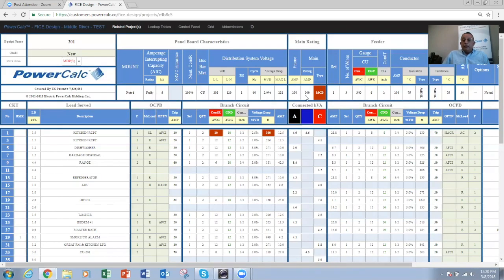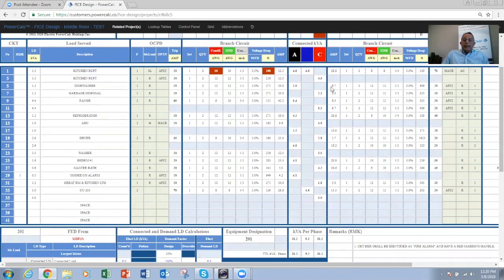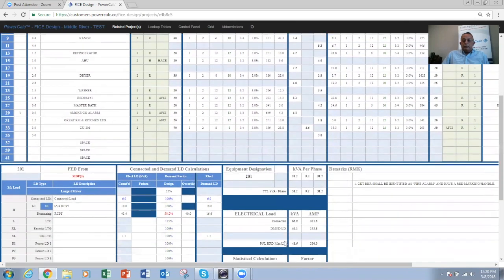It took out the red marking or the red background to indicate to you now you are set on auto and it's not on manual anymore. The system by itself already recommended to you that the frame is for 200 and figured out for you exactly the conductor size, 1, 3/0 conductors, and then the ground is number 6 in a 2-inch conduit. And that's based on this particular demand load. Actually, I need to put an AC here. Calculate.